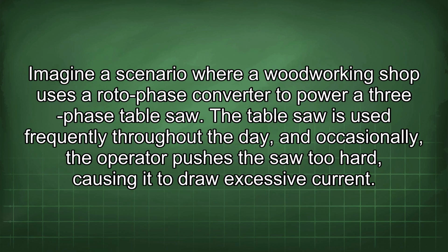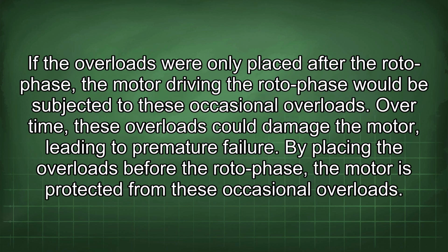Imagine a scenario where a woodworking shop uses a roto-phase converter to power a three-phase table saw. The table saw is used frequently throughout the day, and occasionally the operator pushes the saw too hard, causing it to draw excessive current. If the overloads were only placed after the roto-phase, the motor driving the roto-phase would be subjected to these occasional overloads. Over time, these overloads could damage the motor, leading to premature failure.